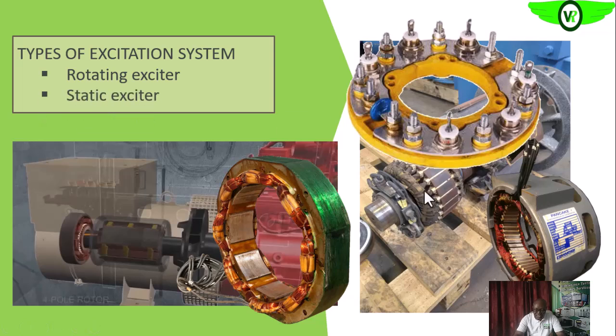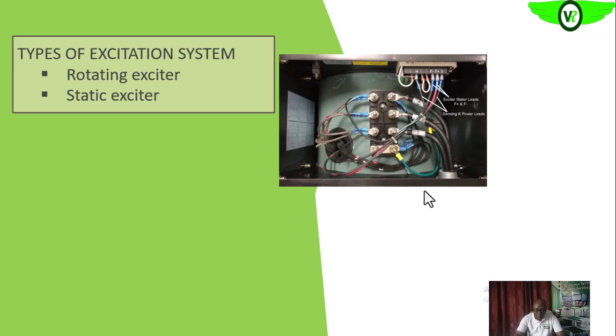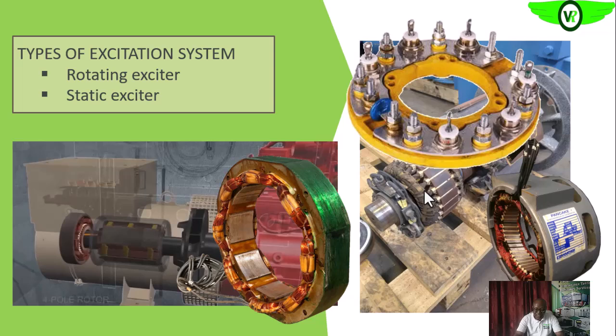The next is the static excitation system. As we said earlier, the exciter is not rotating, it's stationary. It uses semiconductor devices or electronics to do the conversion, as you have on this diode plate, before it is fed to the generator by slip ring.